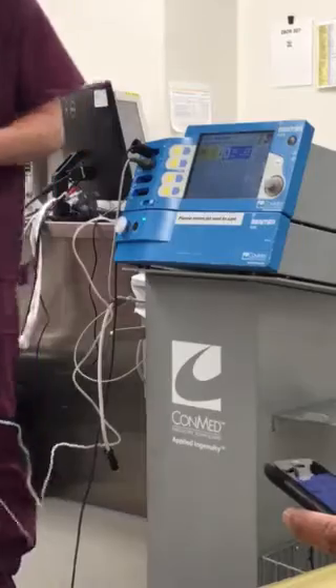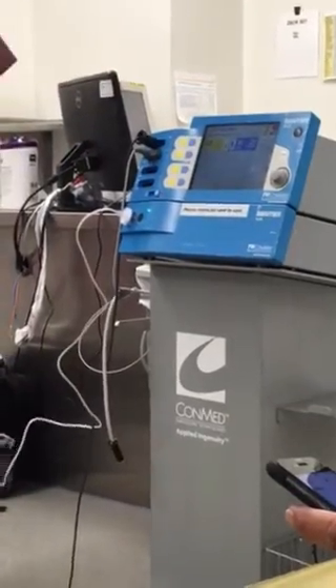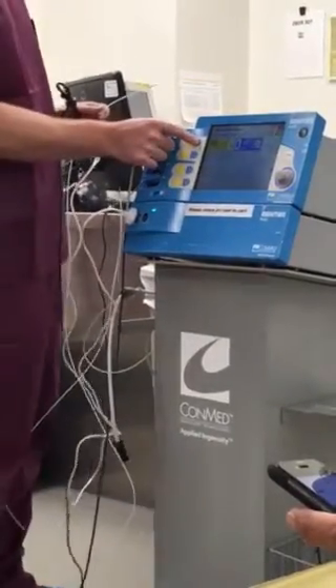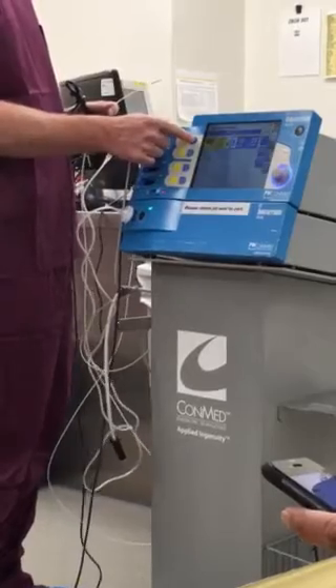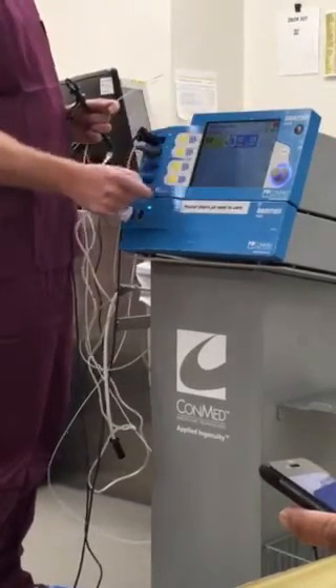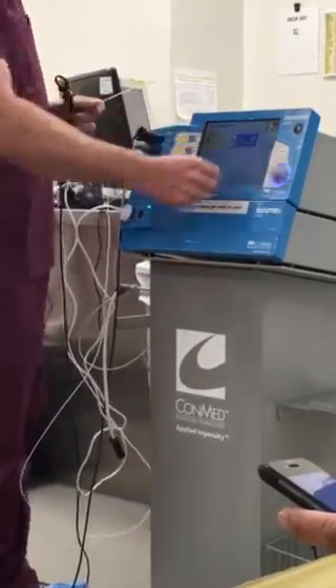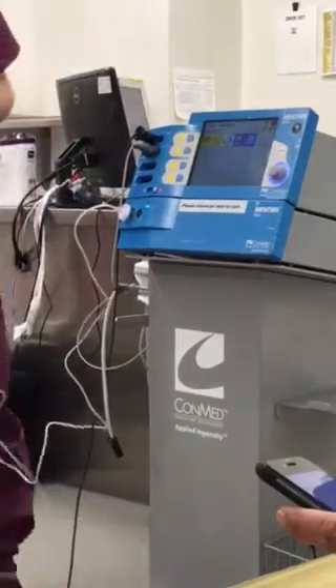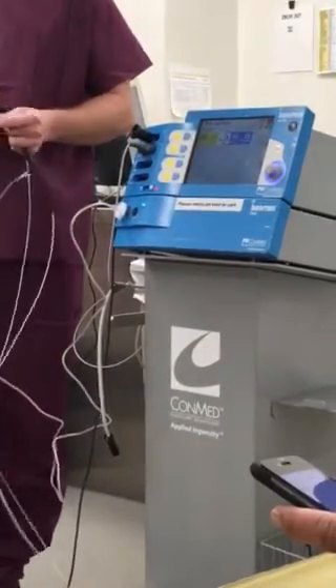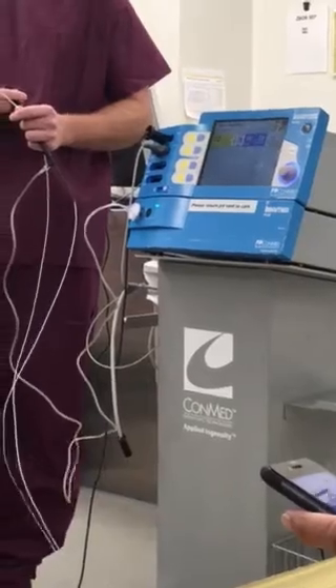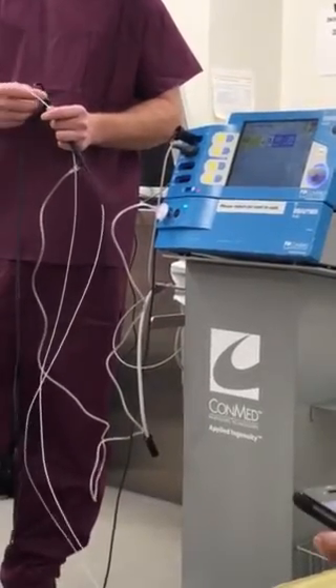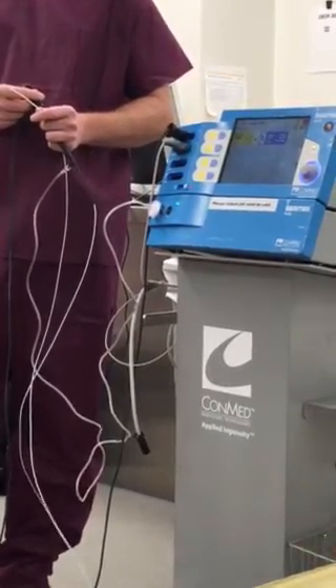They may want to adjust the flow rate. The flow rate is going to be this 0.4 right here, and that's based on liters per minute. That's the amount of gas that's coming out of the probe. To adjust that, if you just keep hitting this blue button, you'll highlight that, and now you can adjust that. 0.4 is probably standard for pulmonary. You could go up to like 0.6 or 0.8 if you need to. What is that again? Liters per minute is the flow rate of the argon gas.